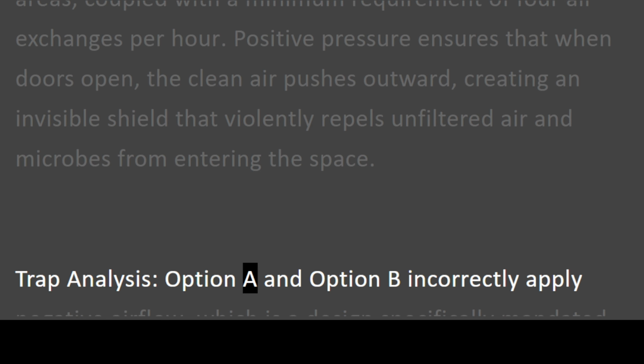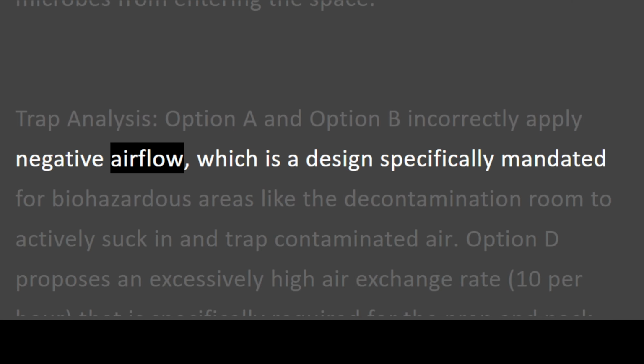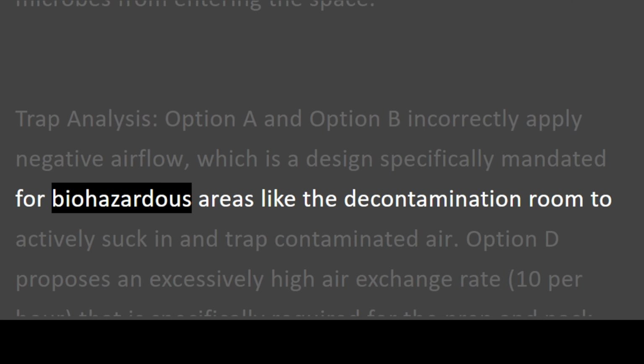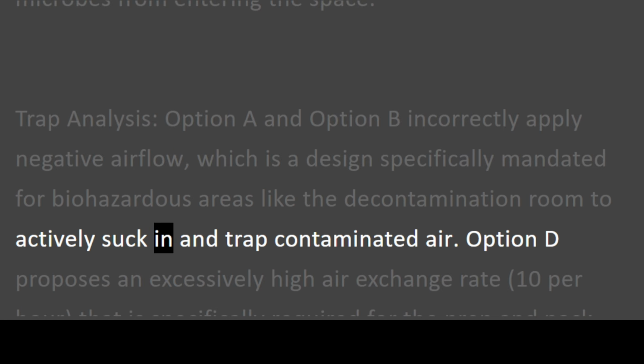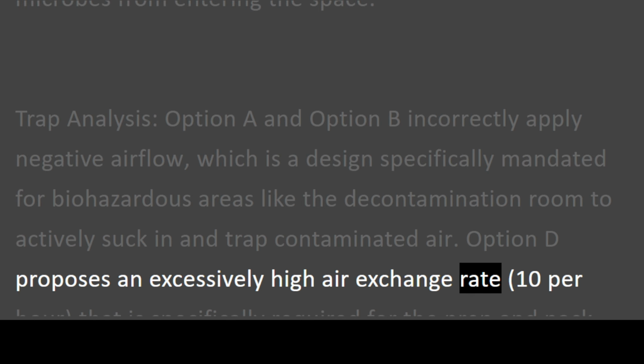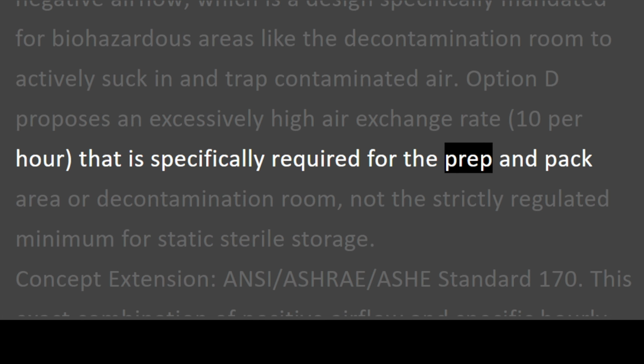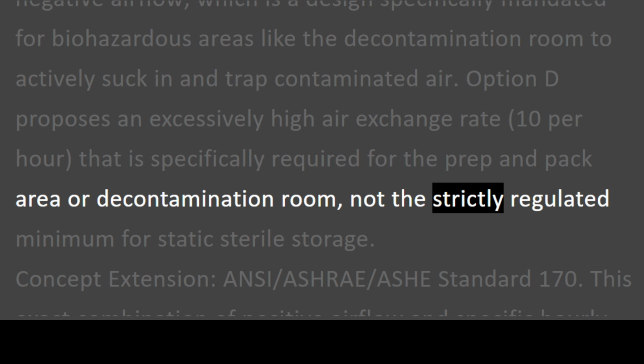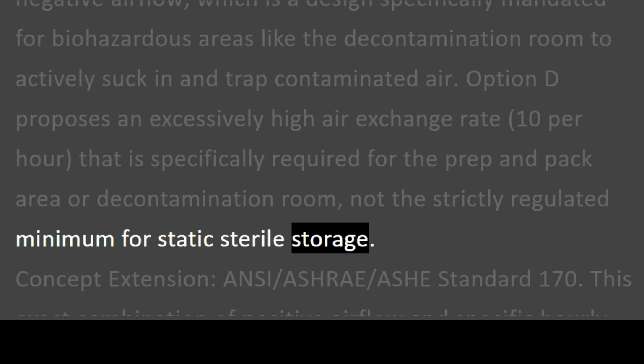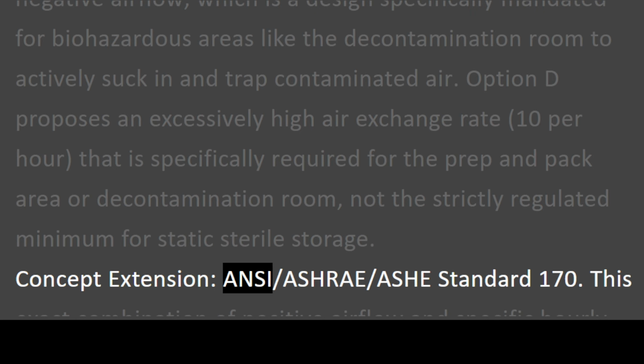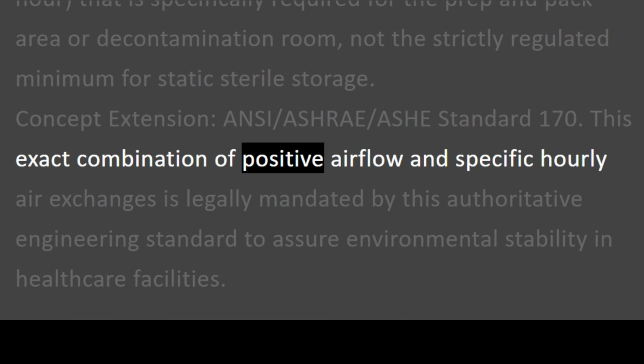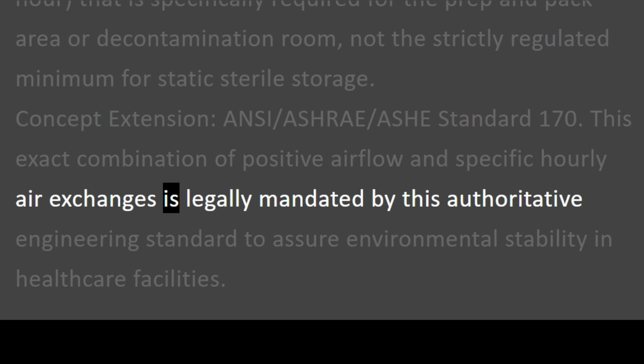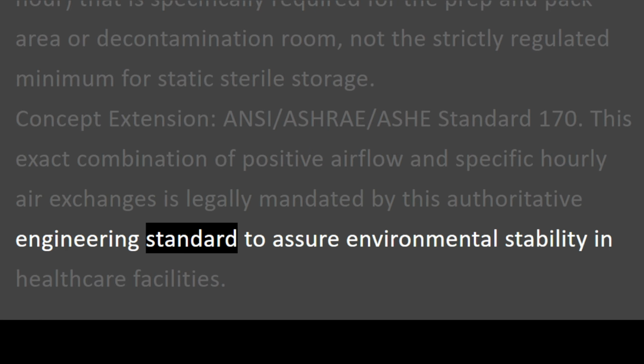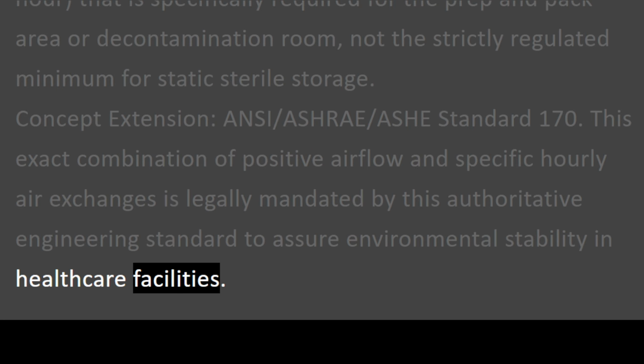Trap analysis. Option A and Option B incorrectly apply negative airflow, which is a design specifically mandated for biohazardous areas like the decontamination room to actively suck in and trap contaminated air. Option D proposes an excessively high air exchange rate, 10 per hour, that is specifically required for the prep and pack area or decontamination room, not the strictly regulated minimum for static sterile storage. Concept extension, ANSI/ASHRAE/ASHE Standard 170. This exact combination of positive airflow and specific hourly air exchanges is legally mandated by this authoritative engineering standard to assure environmental stability in healthcare facilities.